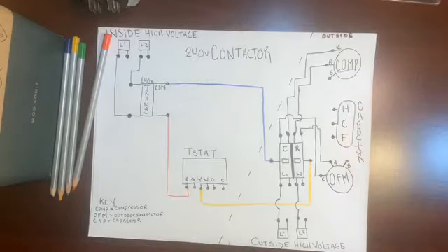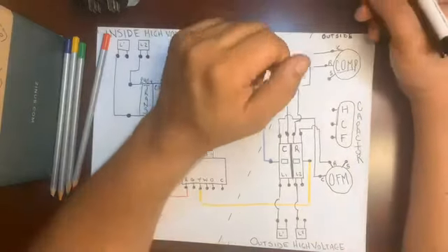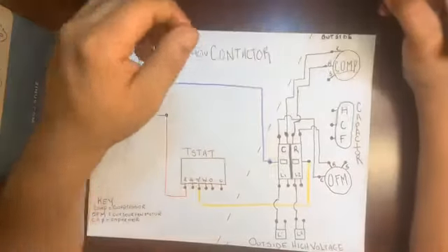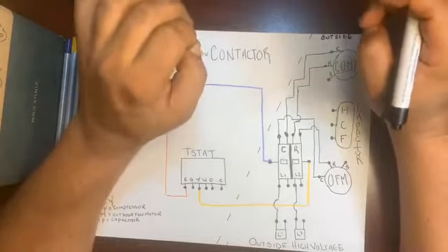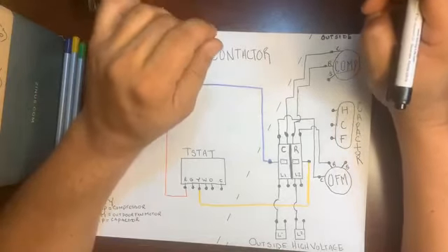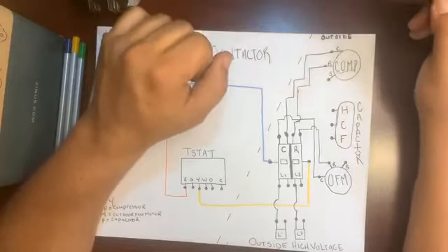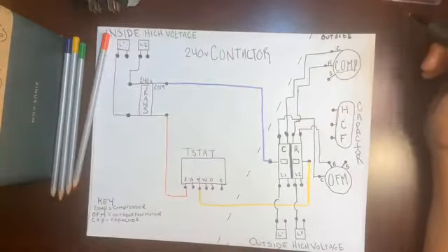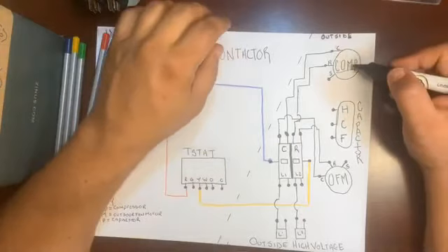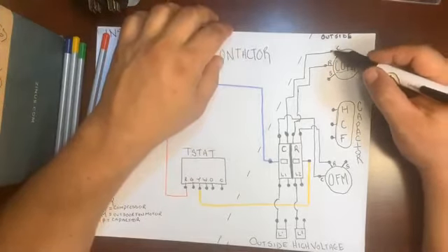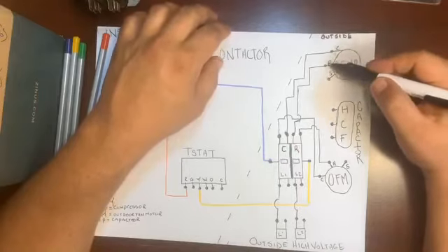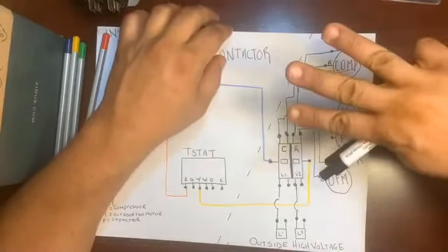So what is a capacitor? You can consider a capacitor as an artificial third leg of energy. So an artificial third leg, might as well say it's a fake leg of energy. Why do we need that? When we look at the compressor, this compressor has 3 lines coming out. You can almost think of them as 3 windings: common, run, and start. That's 3 lines. Outdoor fan motor: common, run, and start.